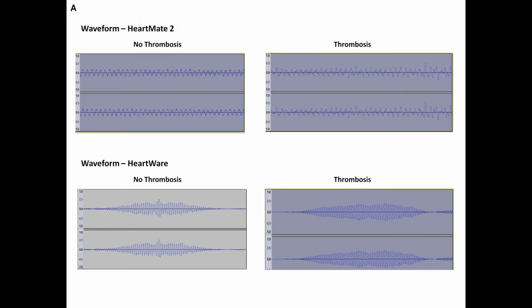So that was the birth of the project, and it was really something that I undertook as a crusade of curiosity. So when we actually went back and looked at the data, the recordings that accumulated with our engineering colleagues, we could see that there were predictable harmonics detectable in all 3 devices we studied, the HeartMate 2, the HeartWare, and the HeartMate 3. And where thrombosis was suspected and ultimately confirmed in patients with the HeartMate 2 device, there was an increase in the relative loudness or amplitude of higher order harmonics. In other words, the higher pitched sound components, the 3rd harmonic in particular.